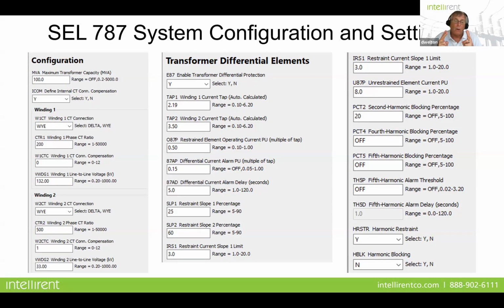Now, most all of your modern digital relays for transformers have this auto tap calculation. But just one little mistake in the information over here on the left-hand side will change these values, and that will give you bad settings. So it's simple if you take your time, and that's the big thing. You can't be in a rush.